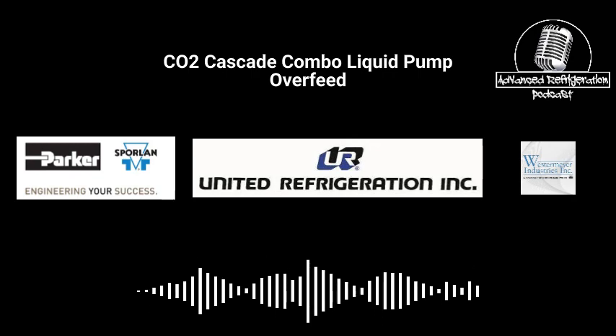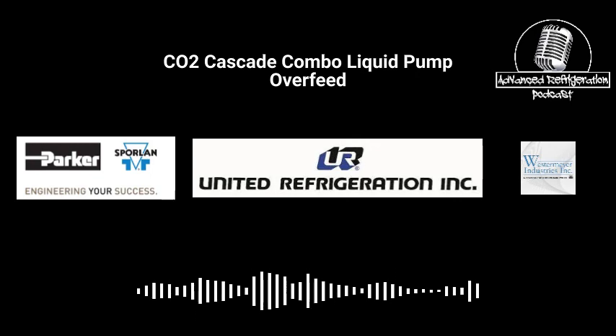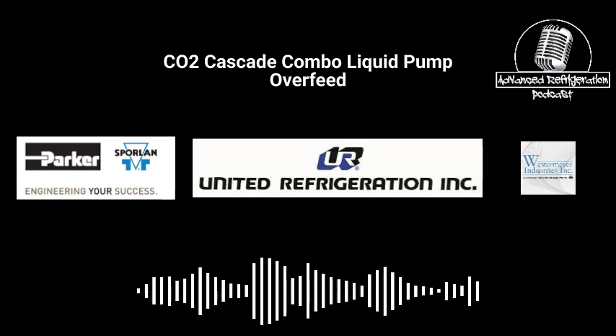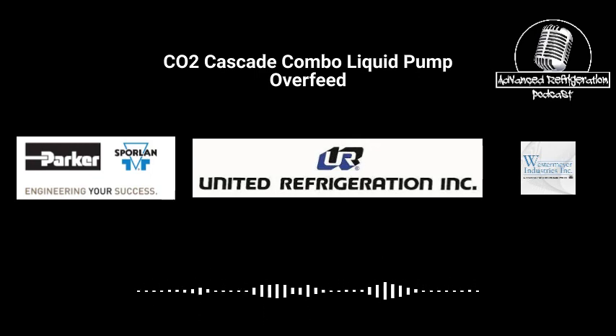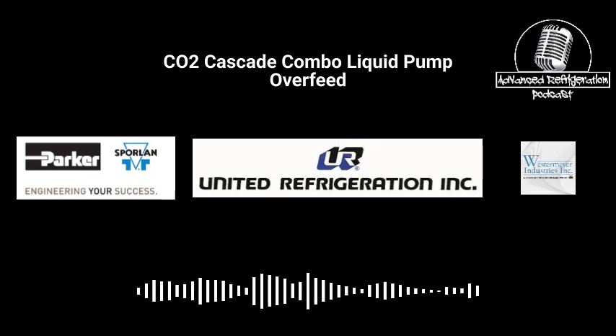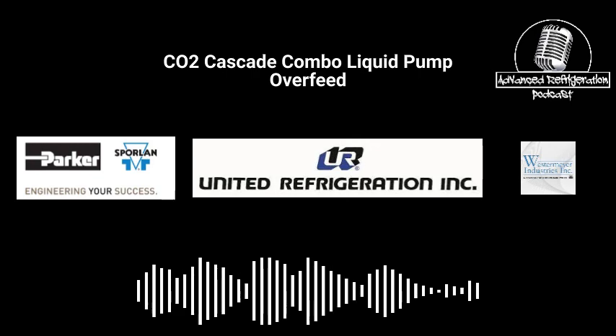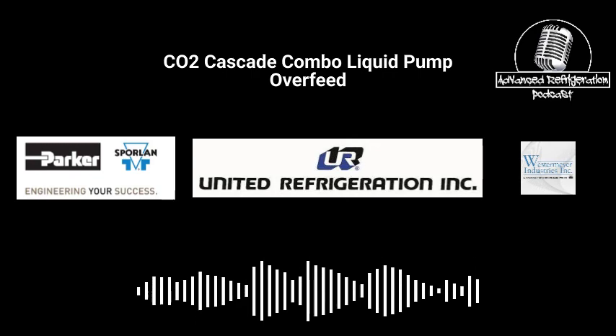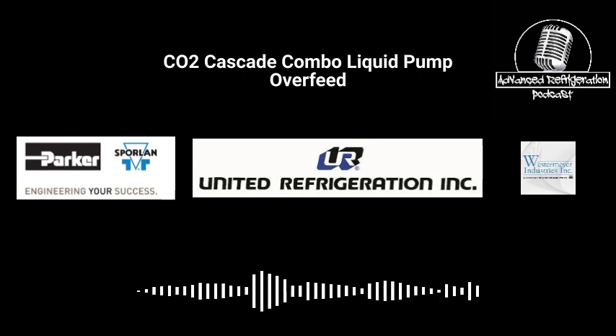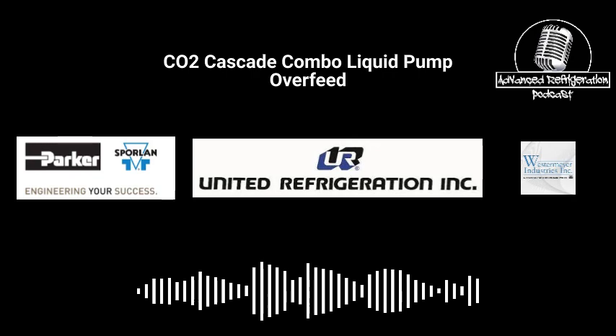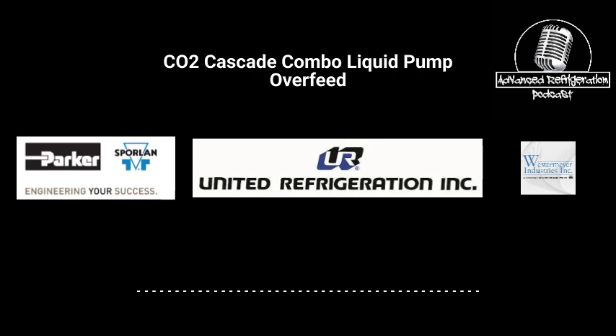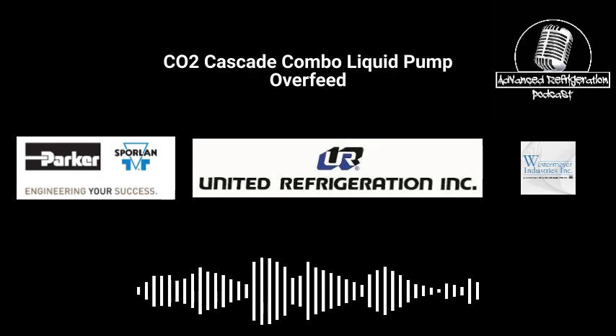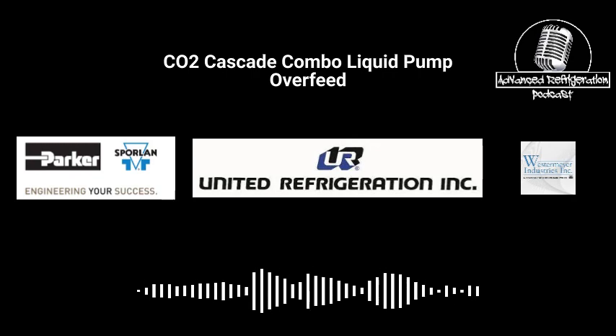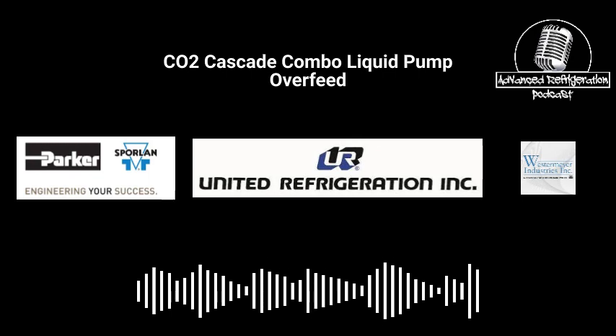We have 2 stores up here, the only 2 that I know of. They run the liquid line through the accumulator. Works phenomenal. Either that or even hot gas, because it doesn't really cost you anything. And if anything, it's lowering your energy bill because you're lowering discharge gas off there. The only thing you have to watch is that you'd need some kind of 3-way valve or something, because you couldn't run the discharge gas through the accumulator all the time. So you would have to have some kind of loop in there, like a de-superheating loop, like with the LMB racks where it bypasses with the EPRs and so on.